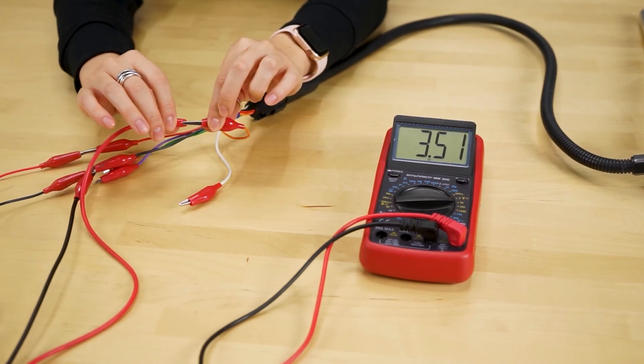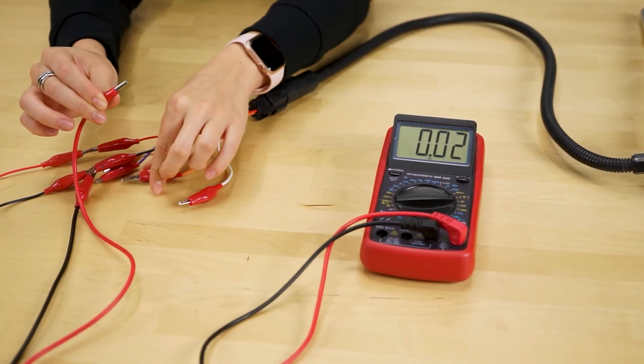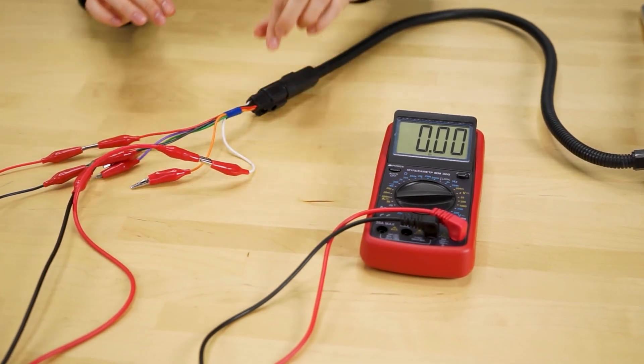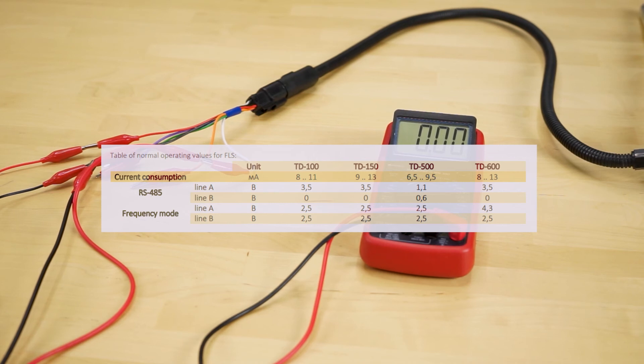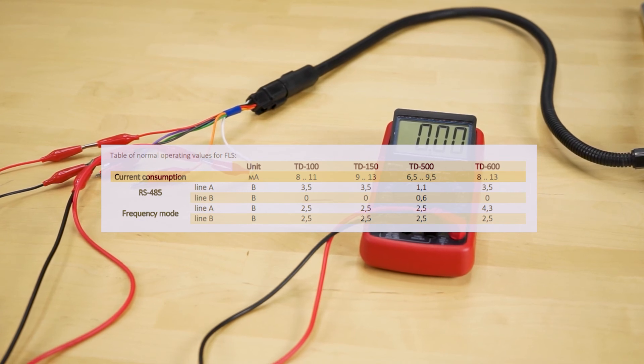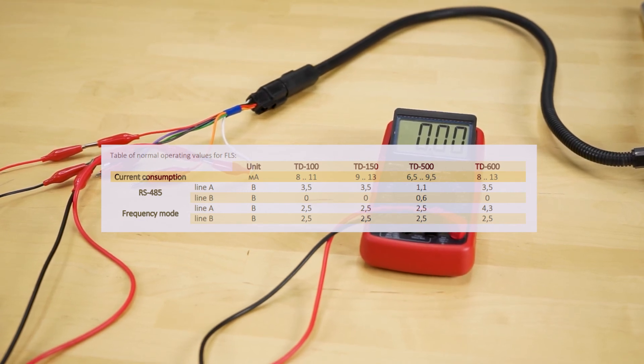If the readings on the multimeter do not coincide with the values of the table, you need to send the sensor to us for diagnostics. If the readings on the multimeter are fine but the device still will not connect, you need to try and update its firmware. We explain how this procedure is done in another video.